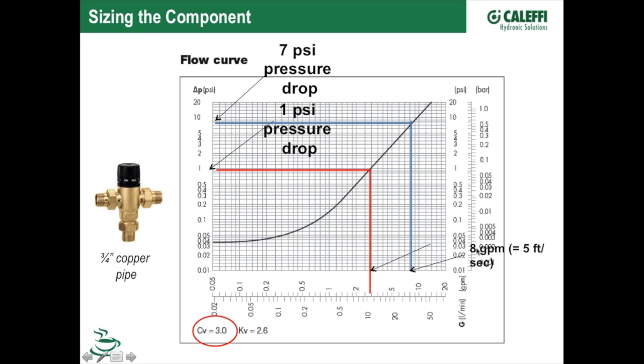So let's go out here, this flow rate. I've got to move my box out of the way, I can't read my... And then we run that flow rate up to the performance line, and now we can see that valve flowing that kind of flow rate is going to have a 7 pound pressure drop. Now that may or may not be a problem with the system. If you've got a customer that's got low pressure coming into their house, let's say they've got a well that only supplies 30 pounds pressure, and you're going to take a 7 pound pressure drop through this valve at that kind of flow rate, that might not be acceptable to the homeowner. They say, where did all my pressure go? And you can hardly take a shower anymore.